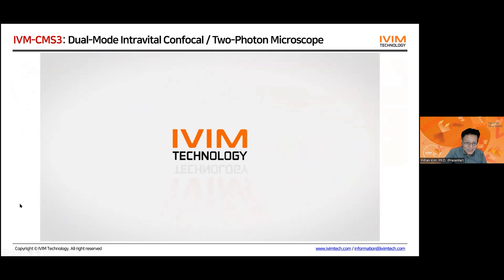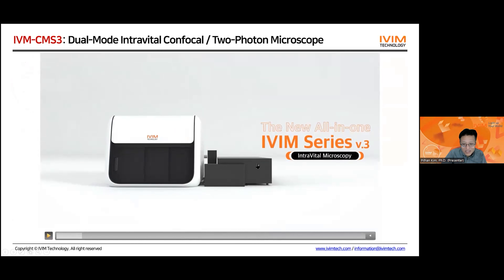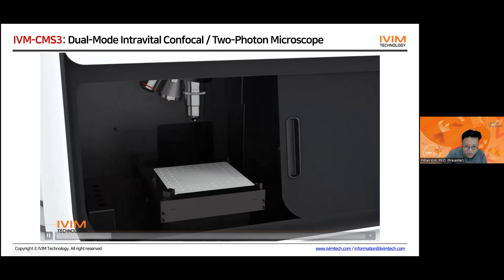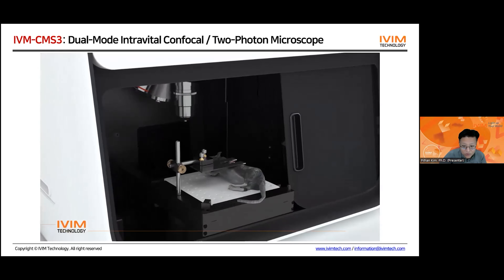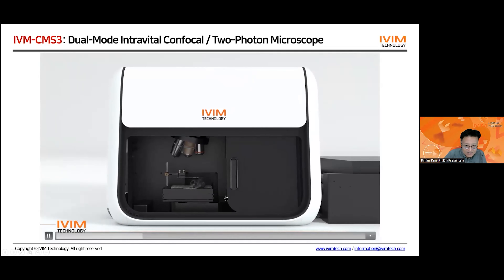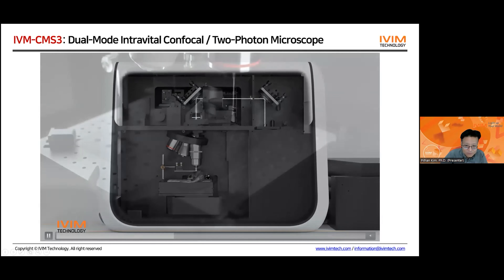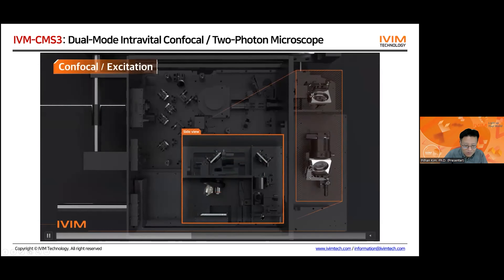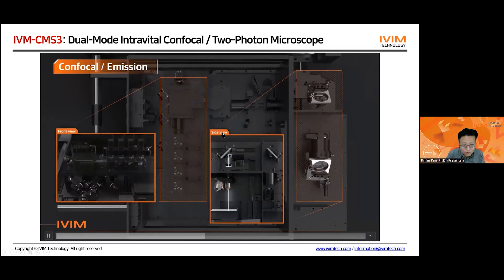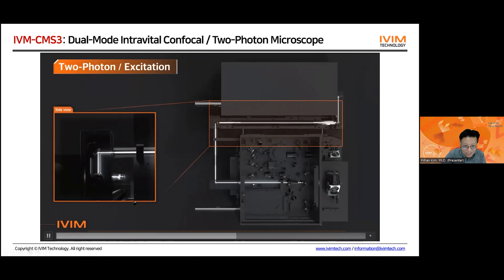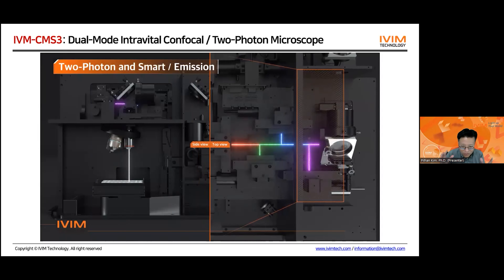In case you want to connect the tunable laser, you can connect it like this to the back of the microscope. It has a single-box design. When you open up the middle, there is a sample stage inside under the objective lens, and you can slide it out to set up the mouse model. You can select the objective lens, close it, and find the focus. It can do four-color confocal detection and also four-color two-photon imaging, in sequential manner, but within the same single-box system.